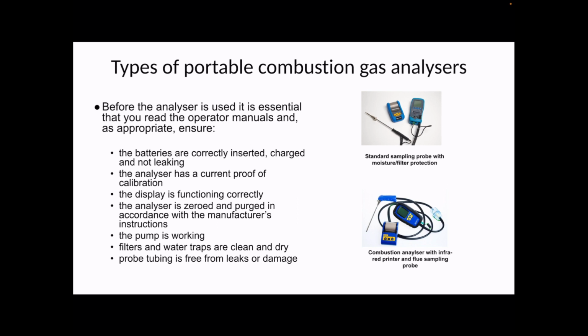Before you use your analyzer, it's essential that you are familiar with it and that you carry out the following checks. Make sure the batteries are in correctly, that they're charged up, and that they're not leaking. Make sure the analyzer has a current calibration certificate. Usually these last for 12 months. Make sure that the display is readable and is reading correctly.